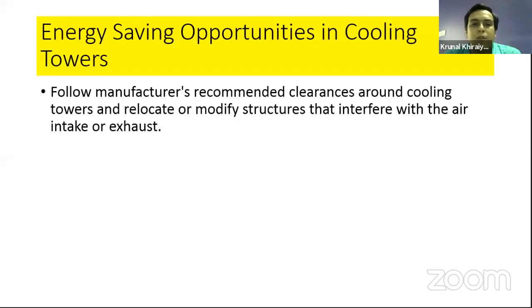Follow the manufacturer's recommendations, clearance around the cooling tower, and relocate or modify it. Suppose whenever you installed the cooling tower, there was open space, there was circulation of water, and wind speeds were maintained. But after a certain period of time, suppose your plant expands and you don't have a fresh amount of fresh air coming to the cooling tower. In these kinds of situations, you need to relocate your cooling tower.